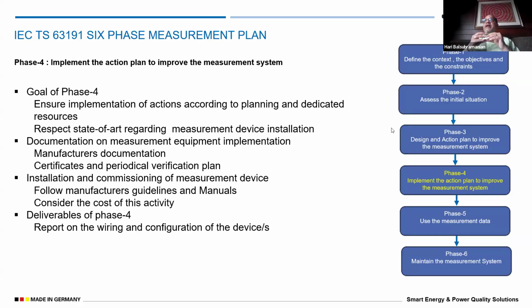You should ultimately create documentation on the wiring, how the meter wiring is done, from which terminal you have taken the CT and VT connections, and how the communication is designed for those meters. The documentation should also include the configuration put in the meters, the CT ratio, VT ratio, and any other memory configuration that exists in the meter, and how it's all done. All these things also need to be documented. That's what this phase covers.